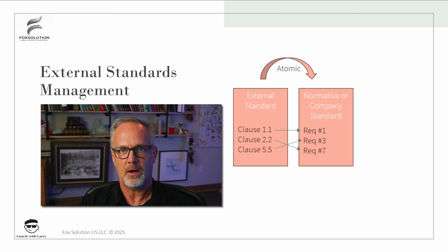One conversation I had a while back was on sterilization of pacemakers, and the way pacemakers are done is in much, much smaller chambers, at least at the company that I was discussing. Now, all of the details around how to do that versus doing pacemakers in a 7-pallet chamber, 100,000 at a time, for such an expensive device, there's all kinds of reasons to do it differently. So that normative standard for sterilization of pacemakers was part of the intellectual property of how that company competes in the marketplace. And so whenever you come up with a standard like that, you want to be able to reuse it for the different projects, for all the different pacemakers that you're building.